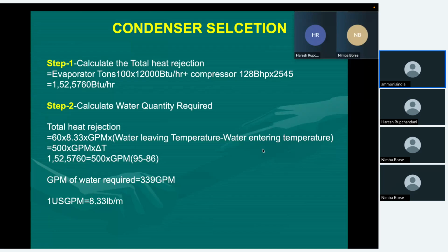Step 2, calculate water quantity required. The total heat rejection is equal to 60 into 8.33. 60 is minutes, 8.33 is pounds per gallon, into bracket water leaving temperature minus water entering temperature. Now this 8.33 into 60 is multiplied. So the normal formula people use is 500 into GPM into delta T.